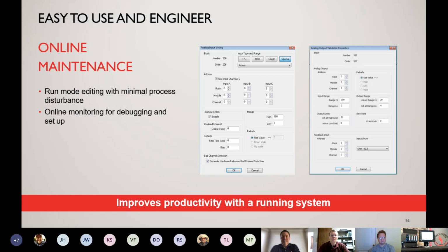It also allows you to do runtime mode editing, which means, let's say for example, I had a process that had 5 thermocouples in it, and I wanted to add a load thermocouple, or I wanted to add a stack temperature thermocouple, or something along those lines. What this allows you to do is, while you're running the process, add that function block to the programming, download it, and go to a hot start. The hot start allows your process to still stay running. It doesn't shut your process down at all, and allows you to add that function block or tag or whatever you might need to add to the programming.